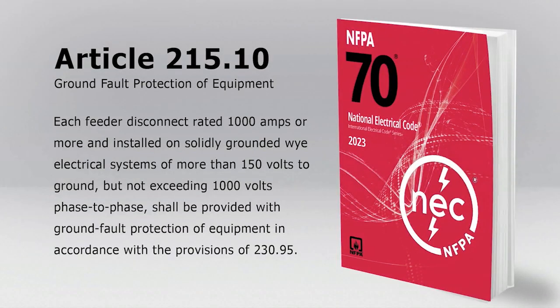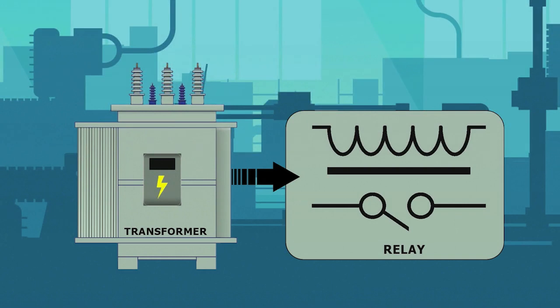So the basic function is this. Typically, you would have the utility service entrance coming in, and that's fed from a transformer, and that transformer will be solidly grounded on the Y connection. That Y connection will go down to the main switch or the main circuit breaker, and then from there it's going to go to feed whatever loads are downstream. So if that system is 1,000 amps or greater, you're going to have ground fault protection on it to clear any faults that could occur. So typically what you're going to have are current transformers to sense the fault. Those current transformers are going to feed a relay which is going to take the fault currents and do something with it. That something is they're going to trip a shunt trip either to open the switch or the circuit breaker. So now we have a ground fault system.